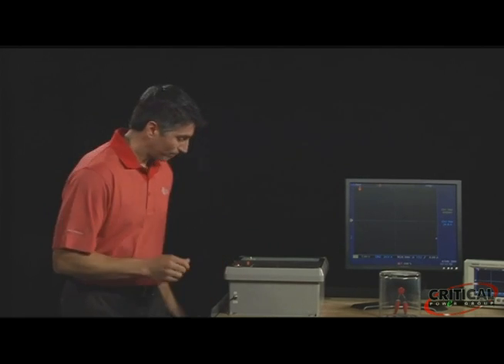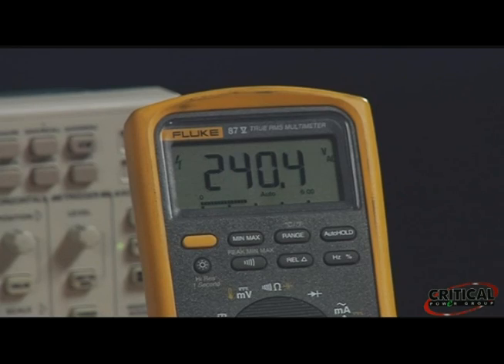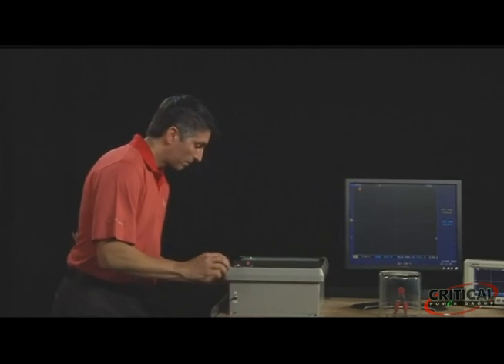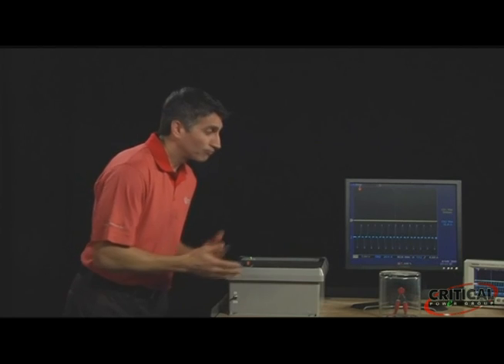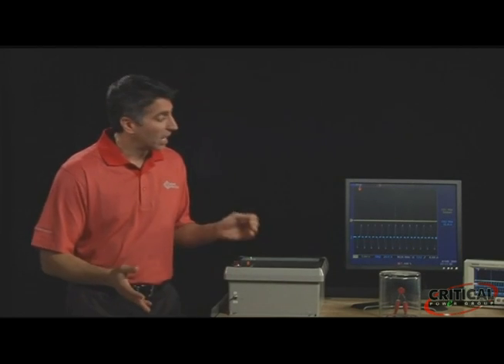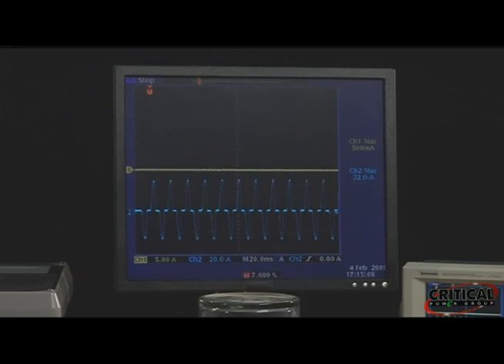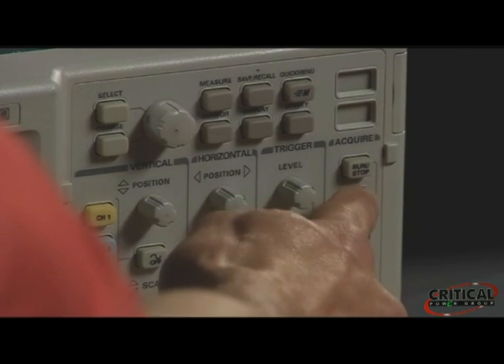Now we'll increase the voltage to 240 volts. Remember that during an MOV-only test, this was the voltage level that caused the MOV to fail. As you can see, the MOV is still intact and has no current activity because the selenium cell is providing all the protection during the TOV event. At 240 volts, the selenium had 22 amps flowing through it. Now I'll reset the scope before the next test.